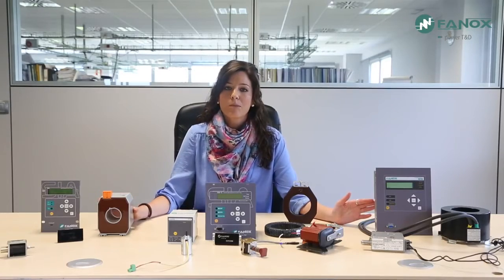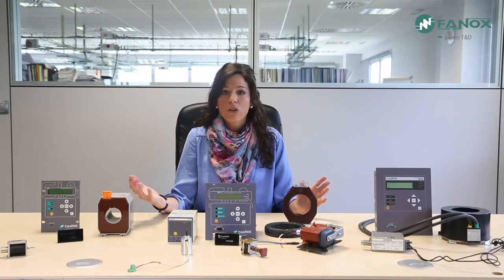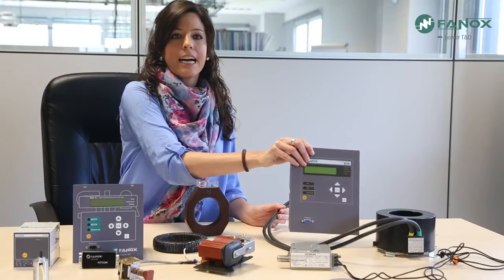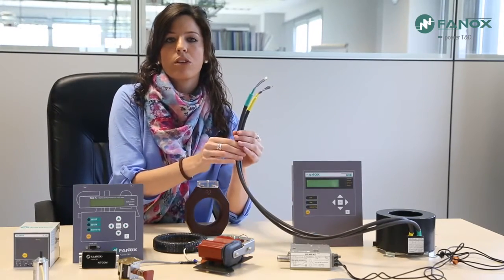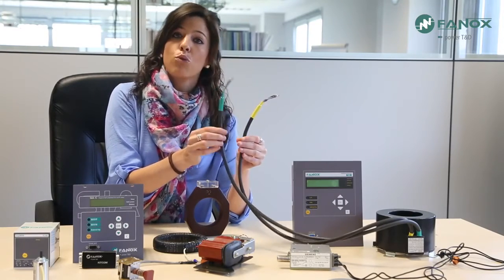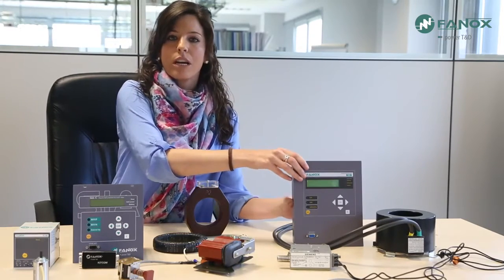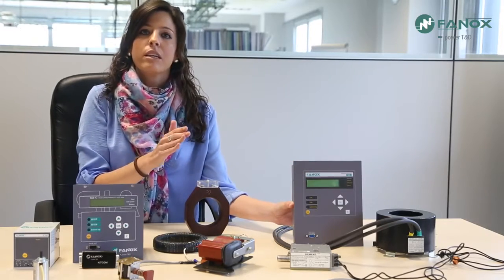The other group of FANOX self-powered relays works with specific transformers. Specific transformers provide special characteristics compared to standard transformers — for example, a higher saturation level, a wider measure range, or double core. In this group, the SIAA relay belongs. SIAA relay works with double core transformers, meaning these transformers have two separated cores with different constitutive materials. This allows one core for measurement and the other for self-powering, enabling the FANOX relay to start up from very low current — approximately 4 amperes.